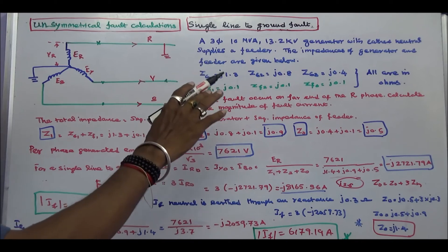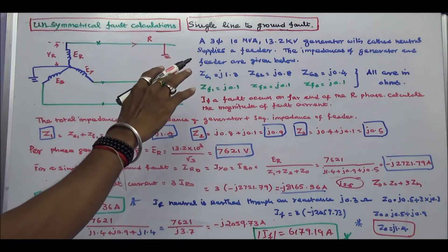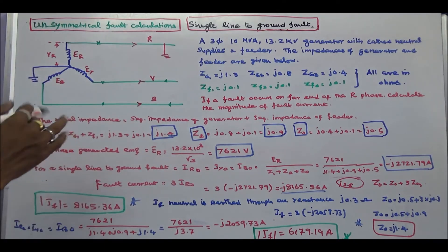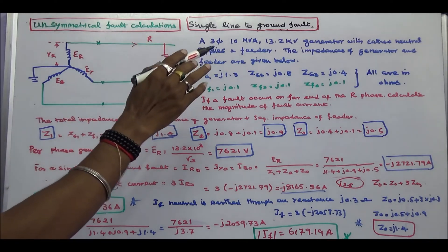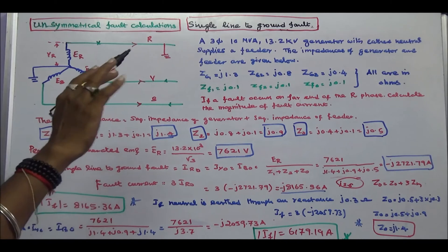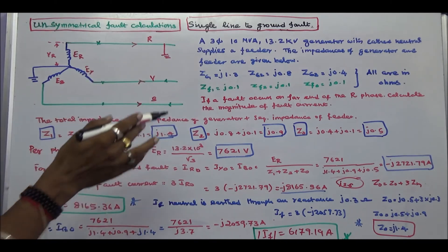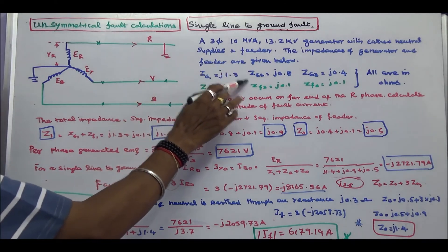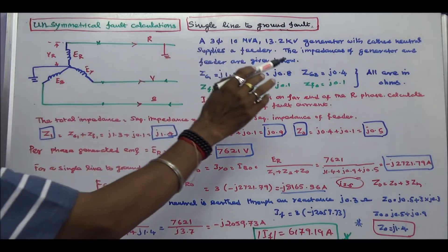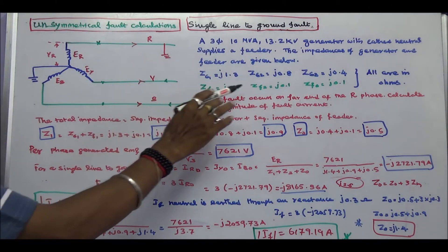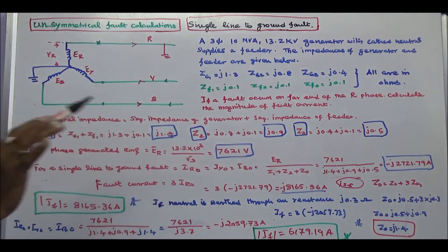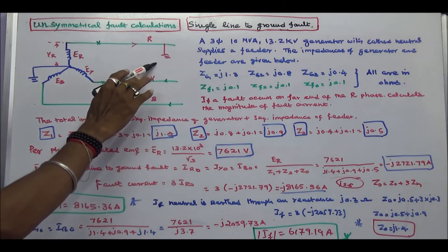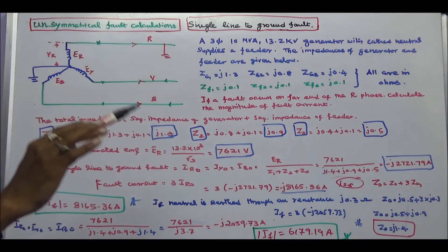The next problem is: a three-phase, 10 MVA, 13.2 kV generator with grounded neutral supplies a feeder. The impedances of generator and feeder are given below, all are in ohms. Positive sequence impedance of the generator is J1.3, negative sequence is J0.8, zero sequence is J0.4. Positive, negative, and zero sequence impedance of the feeder is J0.1. If a fault occurs on the far end of the R phase, calculate the magnitude of fault current.